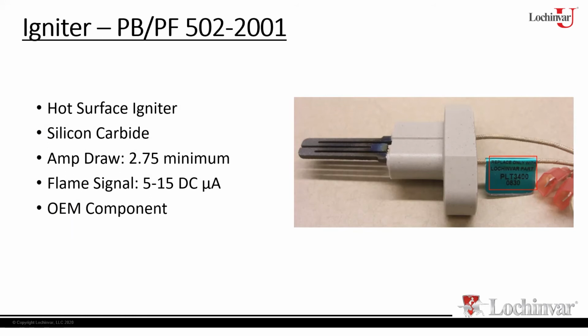Now, you can have an igniter that's glowing cherry or red, but still doesn't draw the right amperage. So we want to make sure that the igniter is doing what it's supposed to be doing. If we're seeing this HSI lockout condition, we look at the amp draw on the igniter. It's got to be above 2.75 amps throughout its cycle. If it drops below that, it's a weak igniter. It's got to be replaced. Typical amp draw on igniters is generally between 3 and 3.5. But again, 2.75 is our threshold.